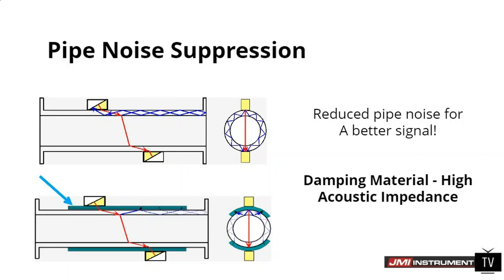The other thing I'll say about this is that you can see these flanges here. These are reflection points. So typically, we don't like to mount these transducers between 3 and 7 diameters of a flange. So either you're going to be farther than 7 or you're going to be less than 3. In a lot of situations, we don't have a choice. We have to go less than 3. But in some applications, especially distribution, we have long straight runs, and we can actually move these transducers out.